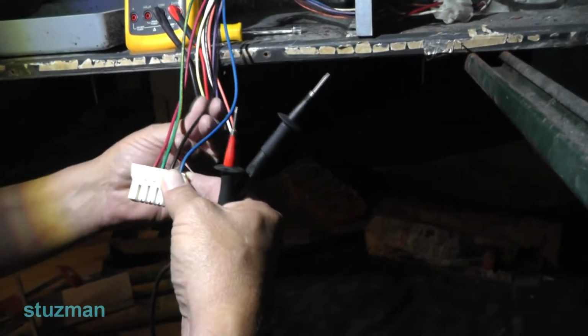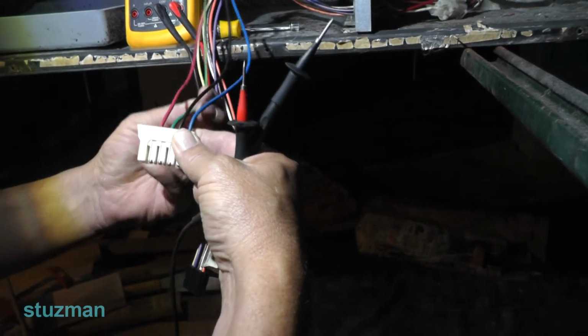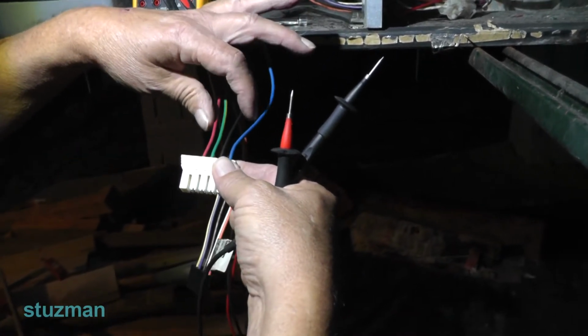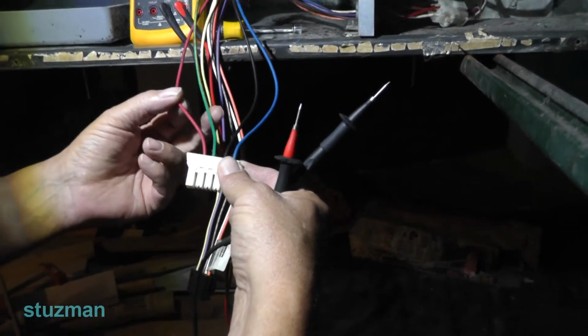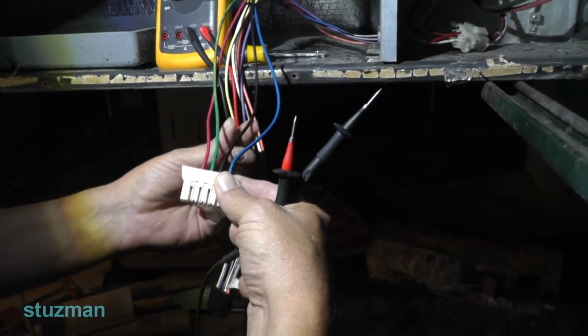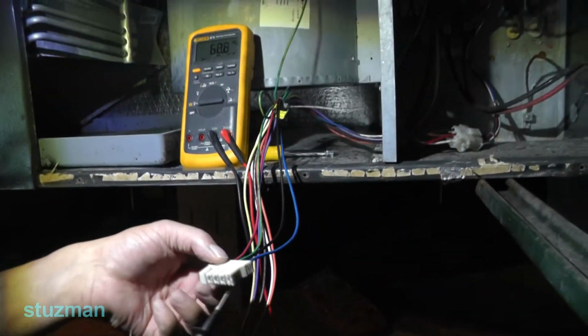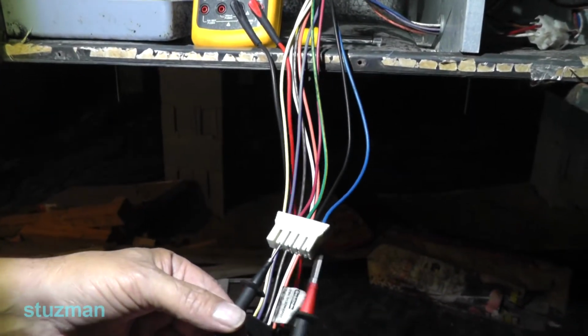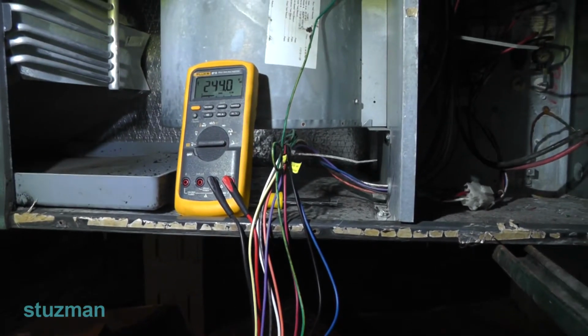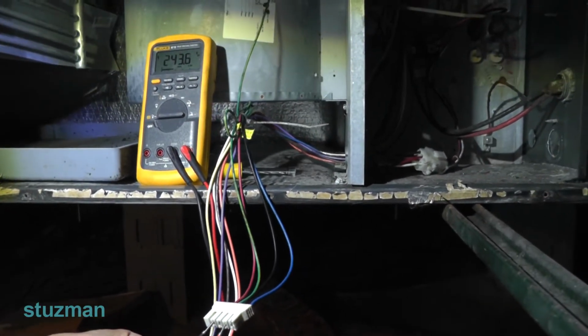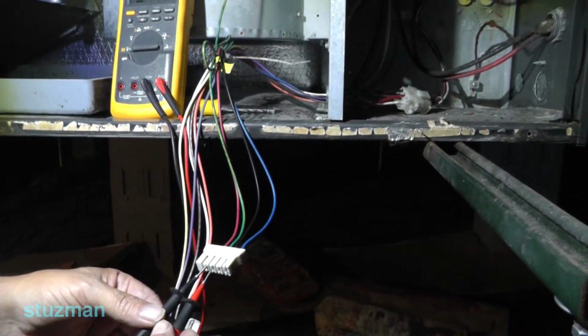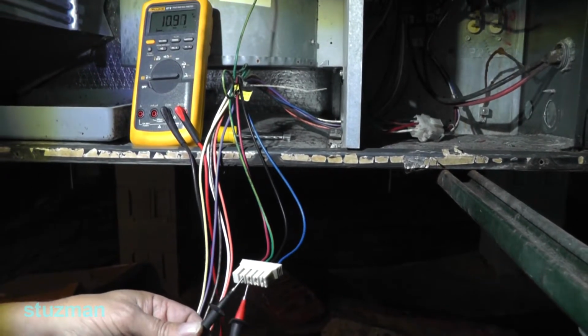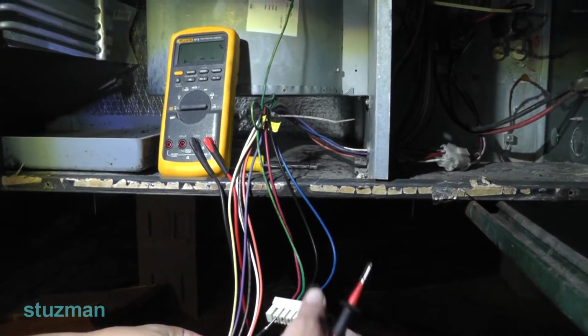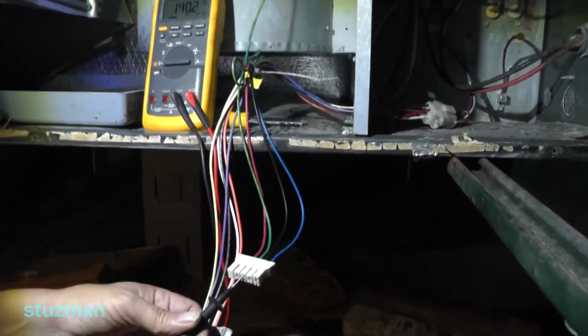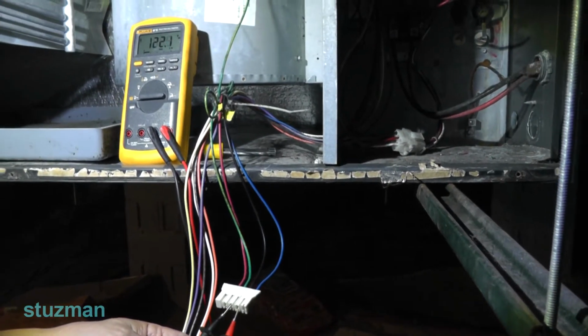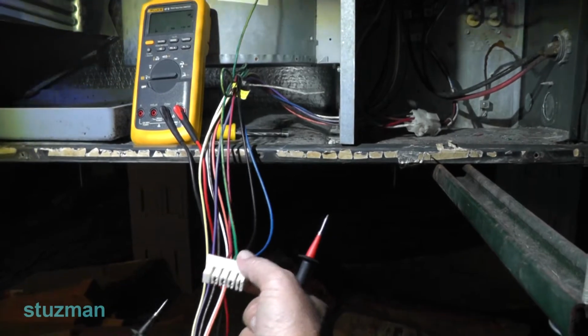Now as you know, the green goes back to the service panel and it is bonded with the neutral. So I should get 240 volts between these two wires, and of course I should get 120 volts between this hot and this ground, which goes back to neutral, and between this ground and the black I should also get 120 volts. So let's check that first. All right, so we got 243 volts there. Now I'm going to go between the red and the ground, and of course I should get 120 volts, 122. Now if I go between the ground and the black, I should get the same, 122 volts. So our line power is there.